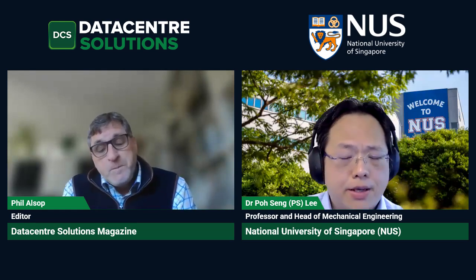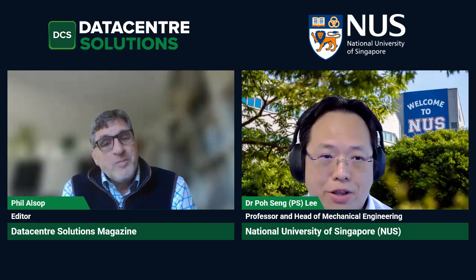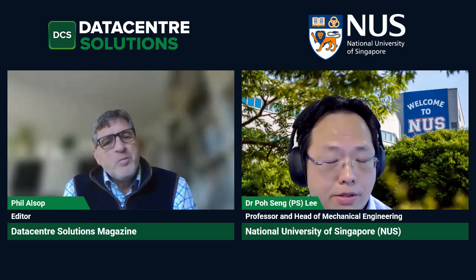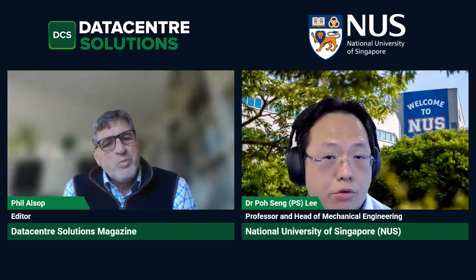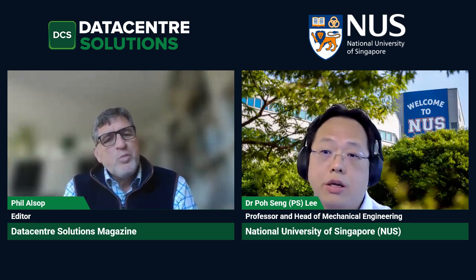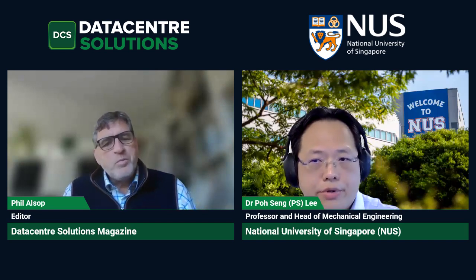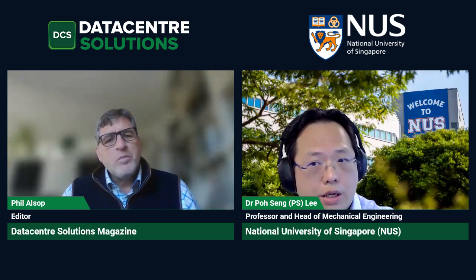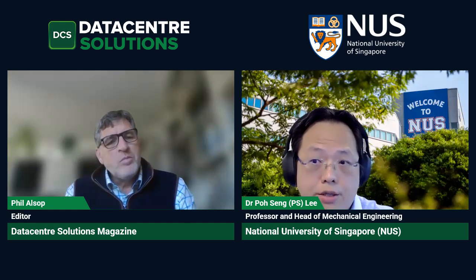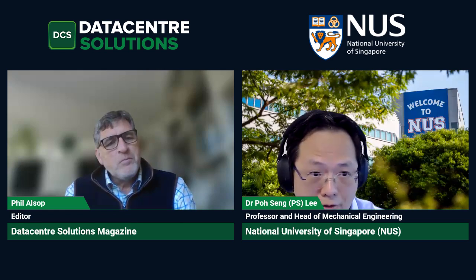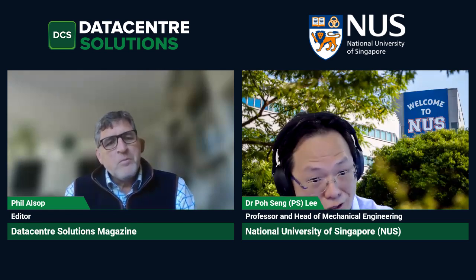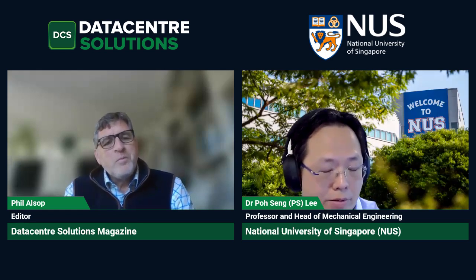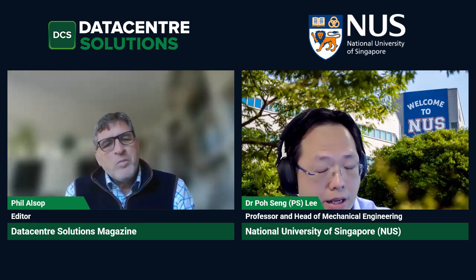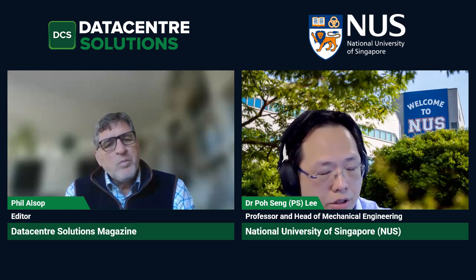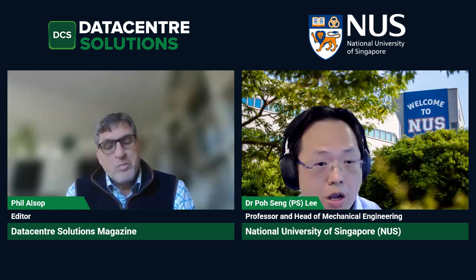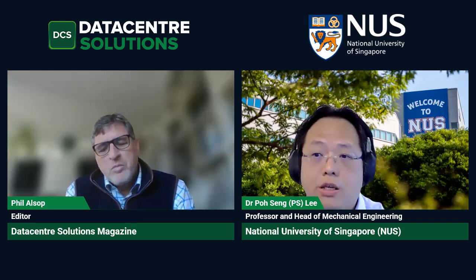Yes, certainly. With thermal design power going through the roof, we have very little option but to start looking at two-phase direct-to-chip or even two-phase immersion cooling solutions. For example, with two-phase immersion cooling, we can look at ways to enhance nucleation at the surfaces, such as using additive manufacturing, which traditionally is an issue for most applications, but the high surface roughness can actually generate additional artificial nucleation sites, which serves to enhance the performance of two-phase immersion cooling.